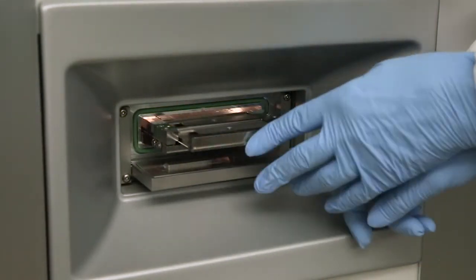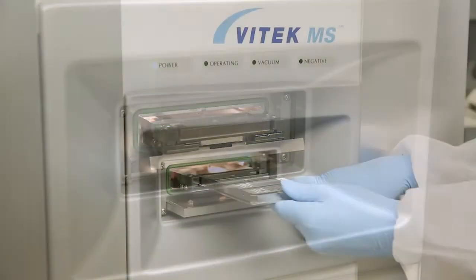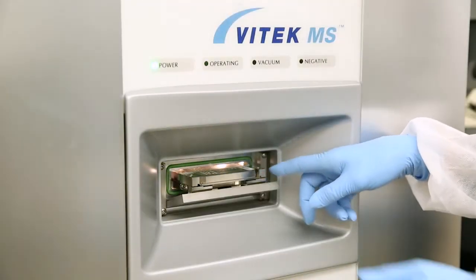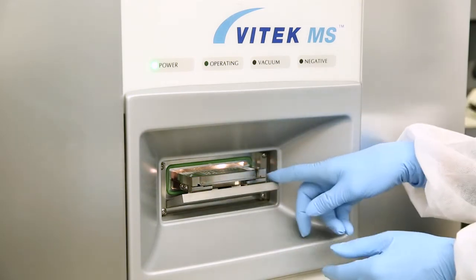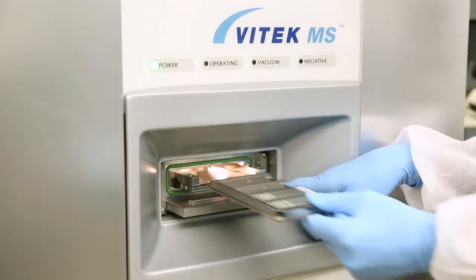Load the slides into the instrument within 5 minutes of the door opening, since the door closes automatically after 5 minutes. Gently slide the adapter into the carrier until you meet some resistance and it will go no further. As you slide your fingers across the back edge of the adapter, it should feel slightly concave. Note, the adapter can be put in backwards but will feel more convex. Testing will fail if the adapter is loaded incorrectly.